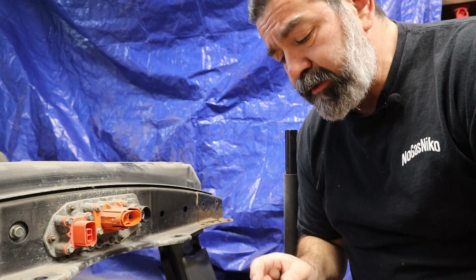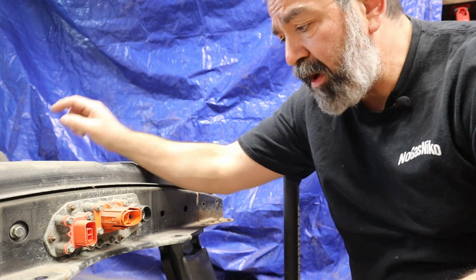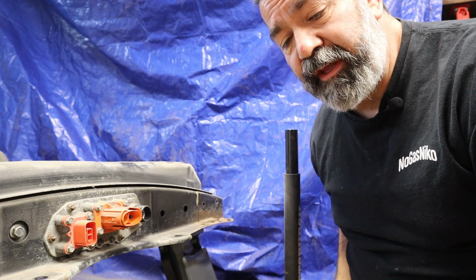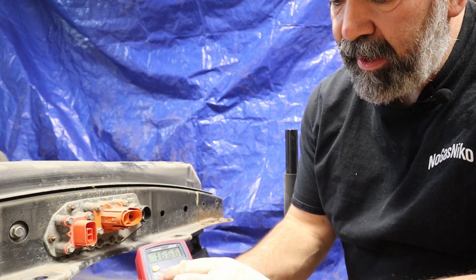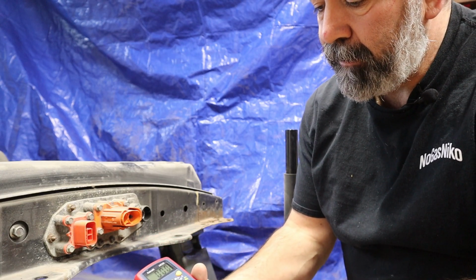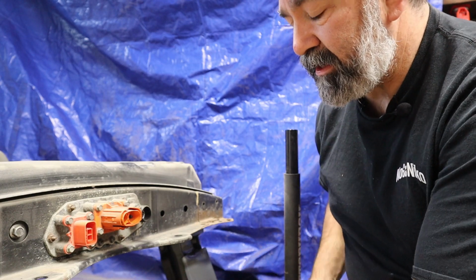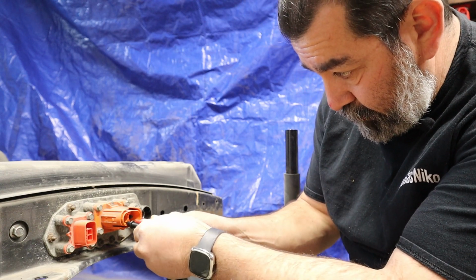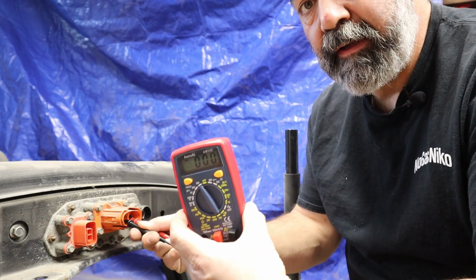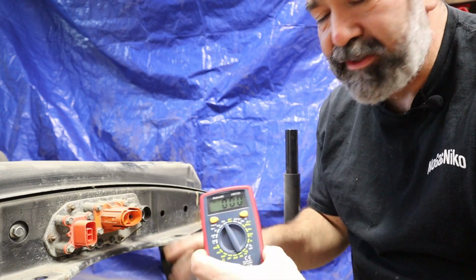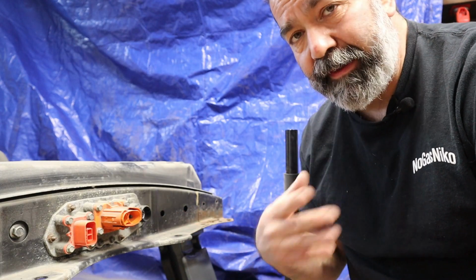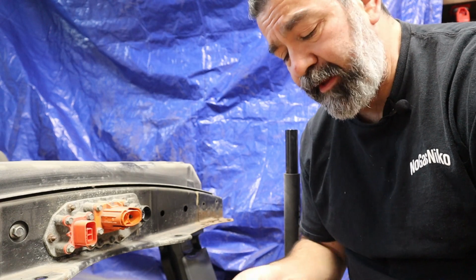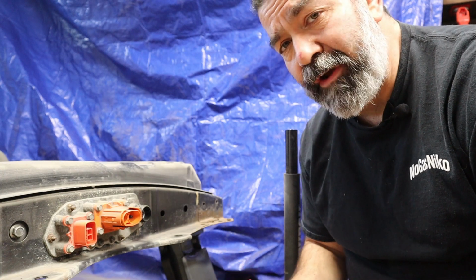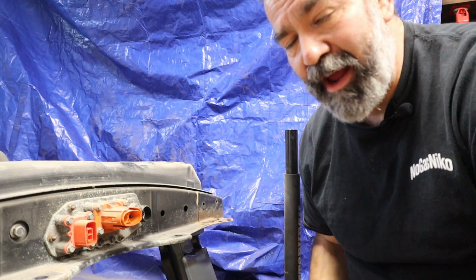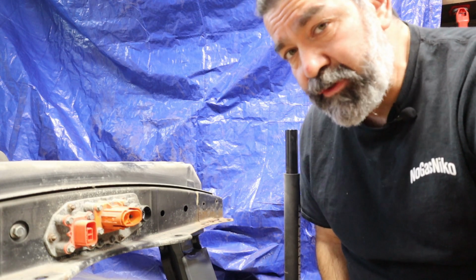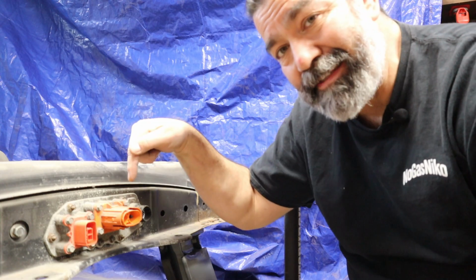First things first, I want to address the concern that somebody brought up on my last video about there may still be power at this plug after removing the safety plug. I'm going to go ahead and turn this on to my DC volts and put it on the 500 range. And you're going to see, I'm going to touch my leads. 0.0 volts. There's no power here. I could touch that with my fingers. I'm not going to because there's superstitious beliefs that somehow that'll be the end of me. So I do know it's safe. I could touch those if I wanted to, but again, there's no reason for me to touch those, so I'm not going to. I touched them with the leads, and they're safe. So there's no power there. Once you disconnect that, this is dead.